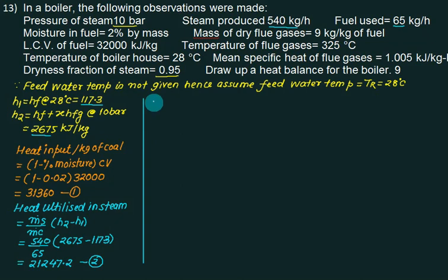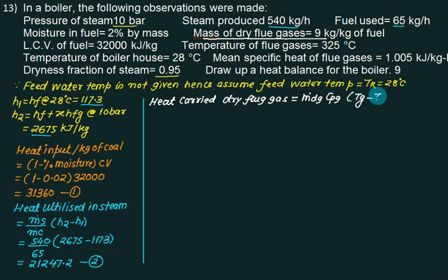Then the third part: heat carried by dry flue gas. He has given the mass of dry flue gas, that is 9 kg per kg of coal. So this is mdg, where DG stands for dry gas, multiplied by Cp of gas, multiplied by (Tg minus Troom). All calculations are per kg of coal. It is already 9 kg per kg of coal. Cp is given as 1.005 kJ/kg K, gas temperature is 325°C, and all quantities are in kilojoules per kg of coal.